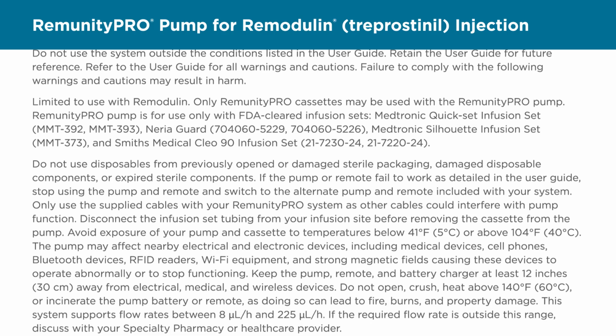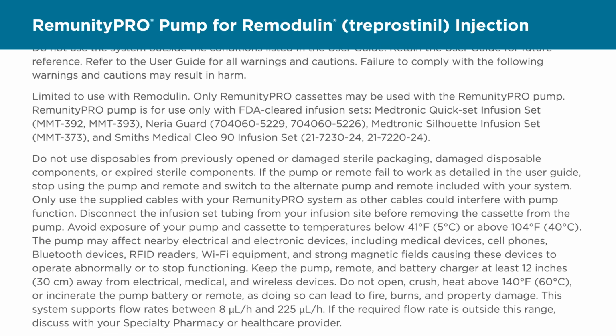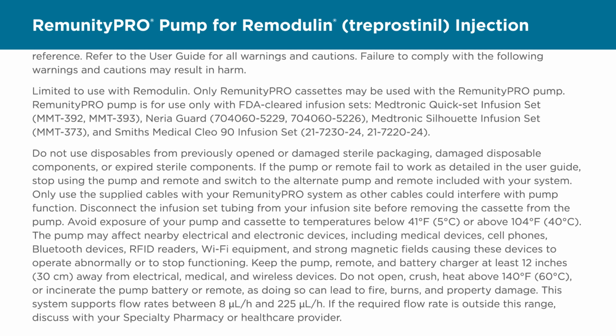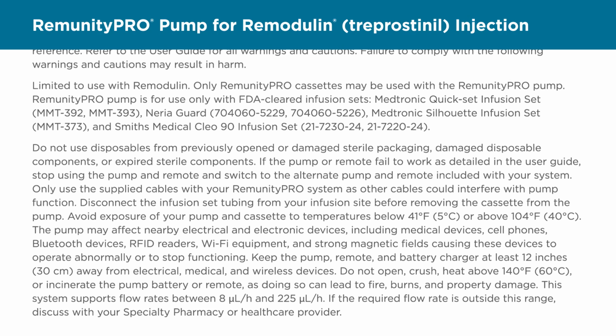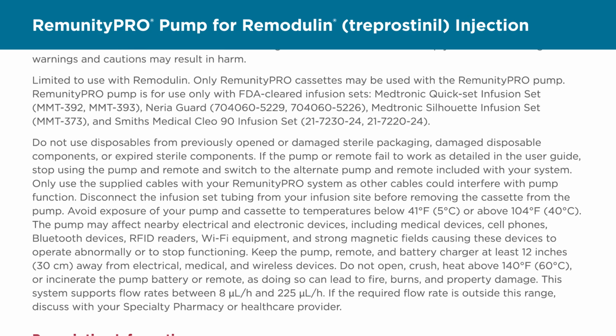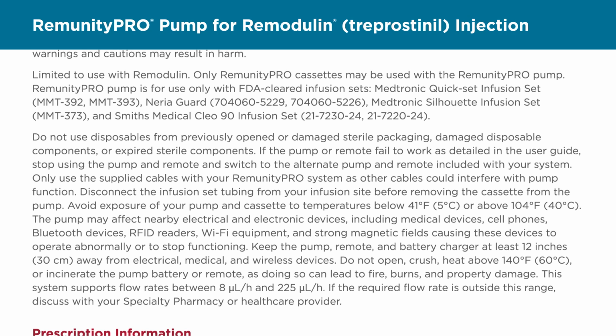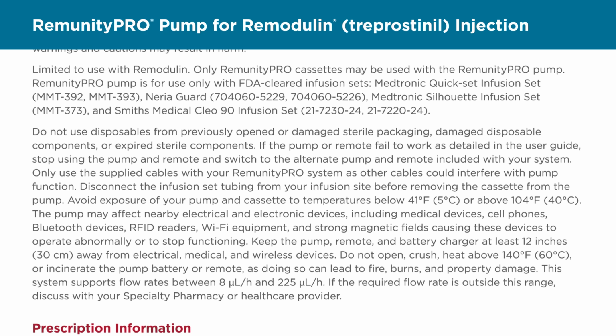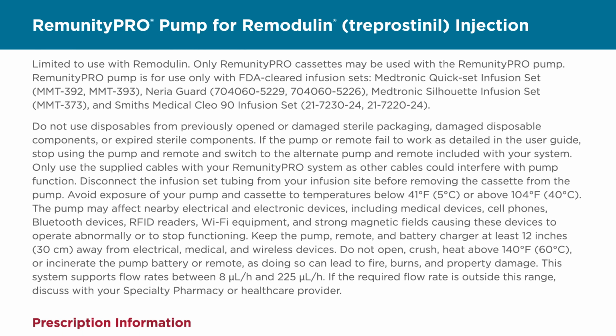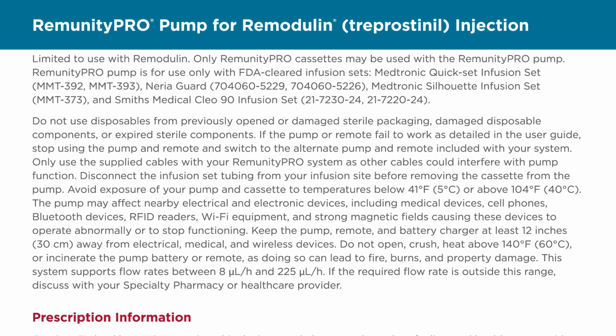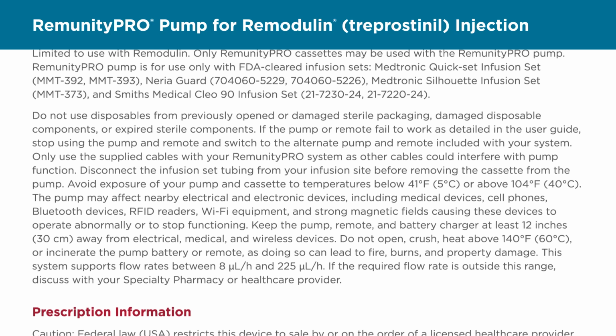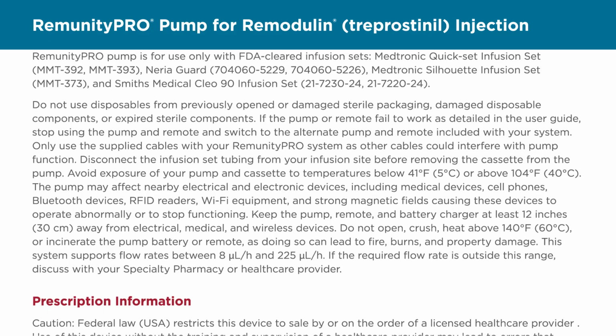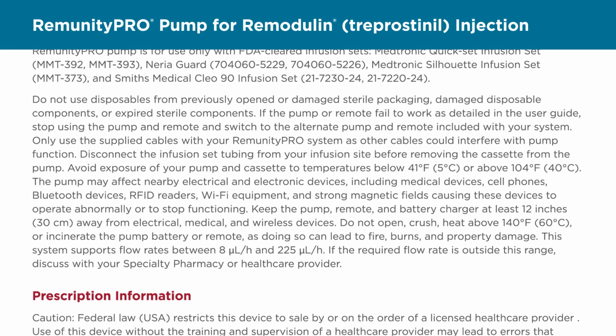If the pump or remote fail to work as detailed in the user guide, stop using the pump and remote and switch to the alternate pump and remote included with your system. Only use the supplied cables with your RemunityPRO system, as other cables could interfere with pump function. Disconnect the infusion set tubing from your infusion site before removing the cassette from the pump. Avoid exposure of your pump and cassette to temperatures below 41 degrees Fahrenheit, 5 degrees Celsius, or above 104 degrees Fahrenheit, 40 degrees Celsius.